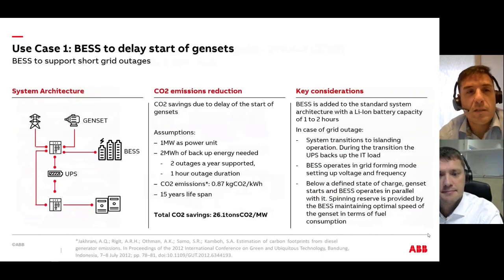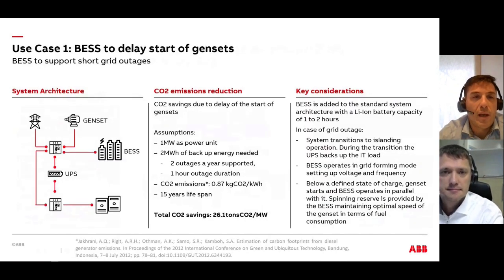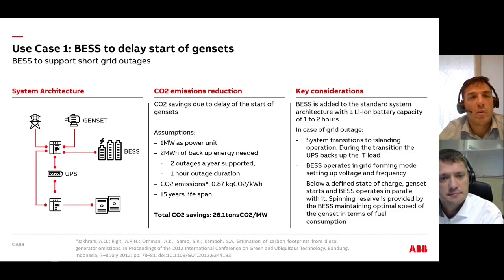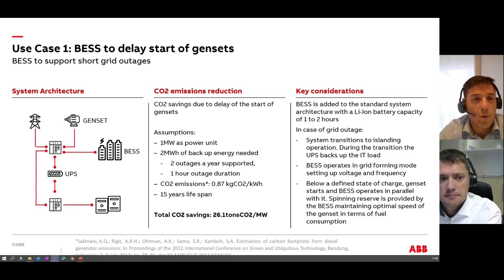If we look at the use case number one that we have here today, the BESS is set up to delay the start of the gensets. So we are going to support those short grid outages up to the duration basically of several minutes or within an hour. The system architecture, the BESS is going to be connected basically in parallel with the genset and with the grid.